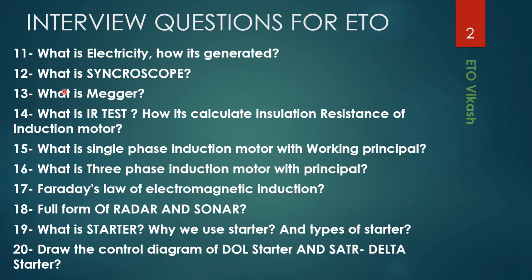Now, what is a Megger? Megger is the company name. It means an IR tester. An IR tester is sometimes also called a Megger. It is used to test the insulation resistance of any motor or transformer. Insulation resistance we can test by this. And how can we test?